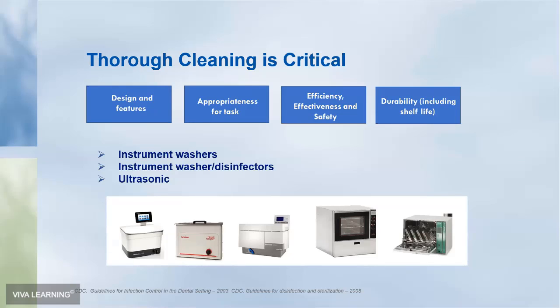If you're using an instrument washer or a washer disinfector, that is fully automated. You can place instruments in there, you can place cassettes containing contaminated instruments in the instrument washer or washer disinfector, and it will run through the whole cycle. It will provide a pre-wash. Cold water will remove the dirt or the soil. There will be a wash with detergents, so that will provide for cleaning. There will then be a rinse. And in the case of the instrument washer disinfector, there will then also be a thermal disinfection cycle. So that uses high temperature water above 90 degrees Celsius. And that actually helps to reduce the microbial load before you go to the next stage.